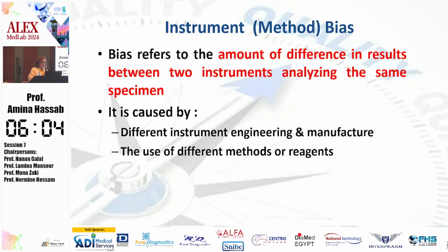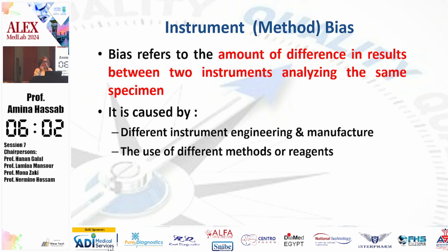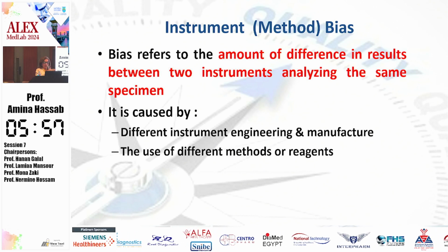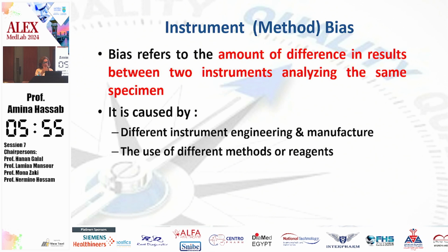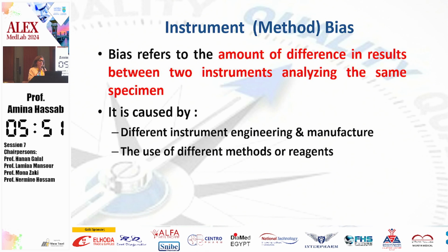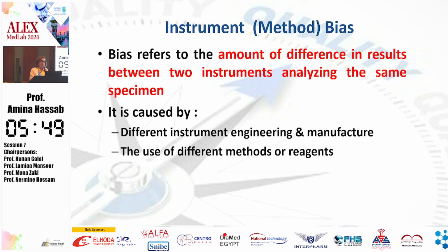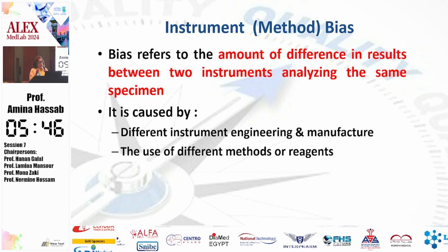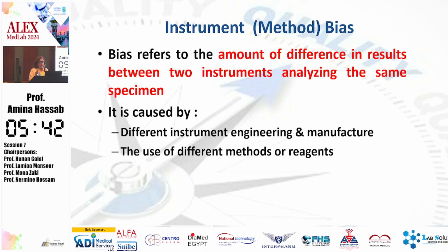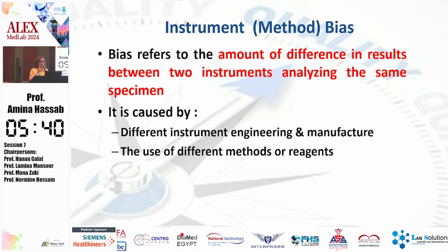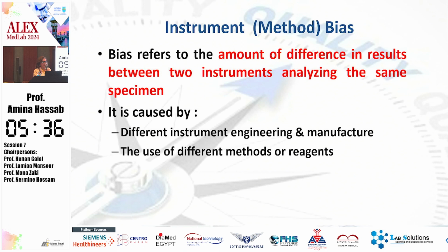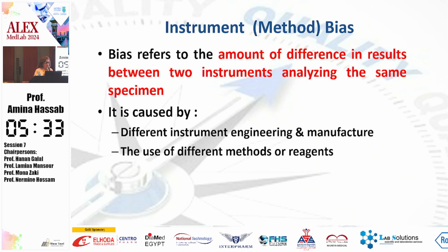Second, we have to think, are we running the test on the same type of instrument and the same method and same reagent, or is there a difference? If we're performing the test on an identical analyzer, same method and same reagent, then I do not need to look for a bias between the results of my analyzer as opposed to the other lab's analyzer.